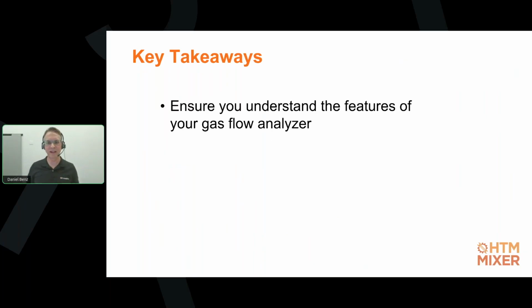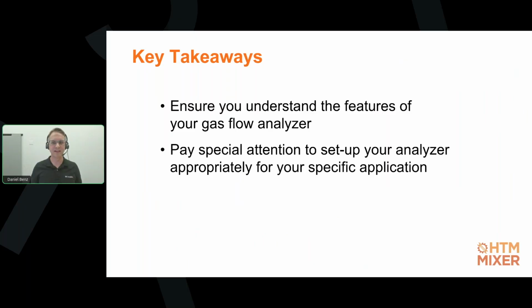Okay, so key takeaways from this session. Number one is that you need to understand the features of your gas flow analyzers. Being aware of what is measured in the flow channels or the different ports is really important, so that you can make sure you have the correct setup for a specific application. Number two is to pay special attention to the setup of the analyzer for your specific device under test. As you've learned in this session, inadequate settings can have a significant impact.